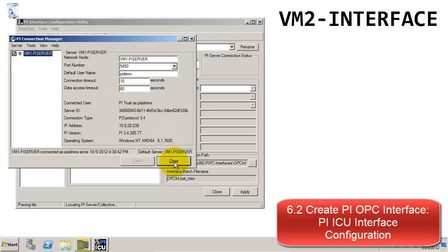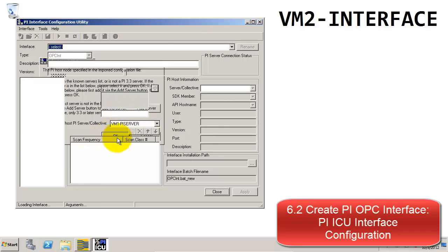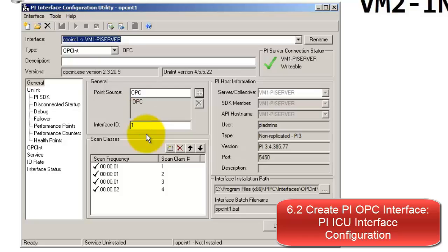We're going to connect, and as you can see, we're now connected as PI Admins successfully. We're going to select the VM1 PI server for our host PI server. When using the ICU to configure an interface, there are a couple of specific items to focus on. The first is the point source — since we have an OPC interface, we're going to leave it designated as OPC. The other key item is the interface ID, which we'll leave at the default of 1. If you have multiple OPC interfaces, you'd use this interface ID to distinguish between them, especially for tag configuration. These are two fields we'll need to specify later when making tags on the PI server.